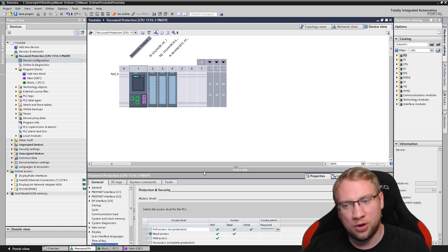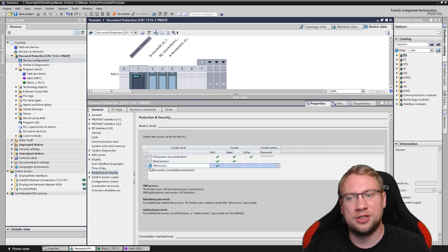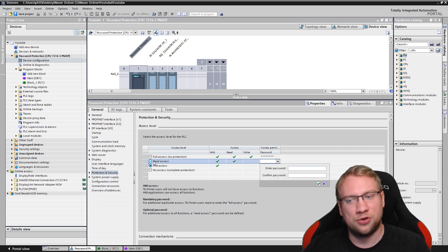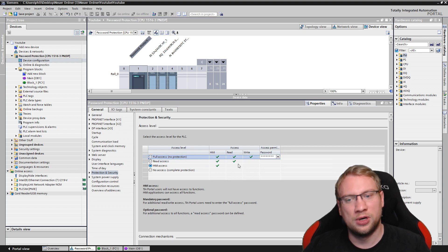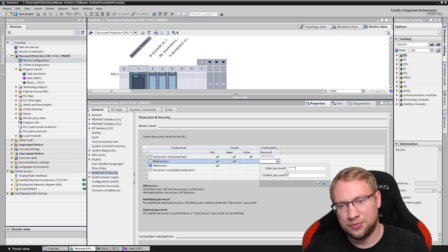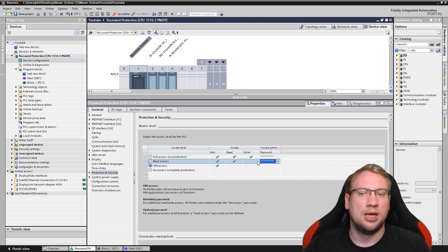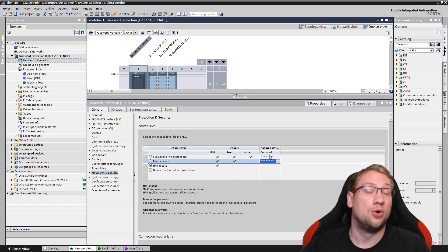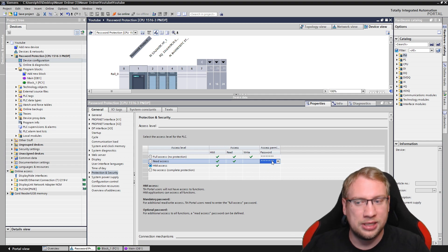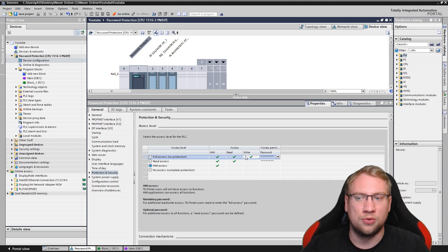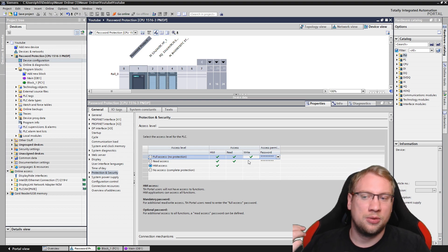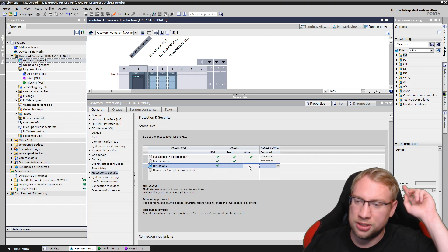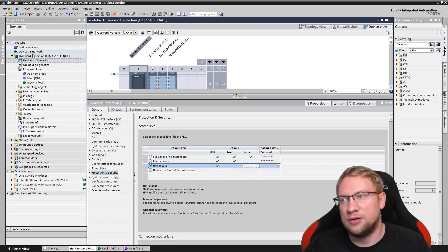We have more levels, right? We have also, if I turn on HMI access, we can now choose a password for read access and one for full access. So I will give this here read, and one for full. I can also leave the read access open, then I only have the full, right? So everyone with the full password can also read. Everyone with the full password can also have HMI access. Everyone with the read access cannot have full access, meaning you can't override stuff. But everyone with the read access can have HMI access, which is HMI data exchanging. So some data exchange, basically. So I now have this.